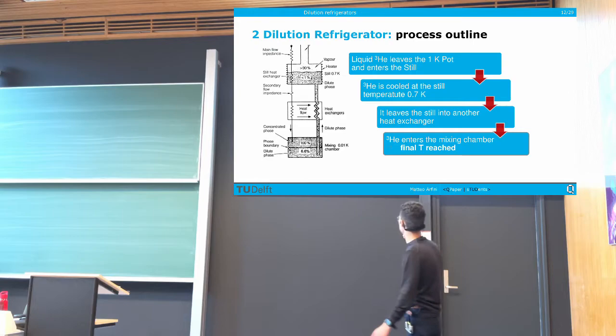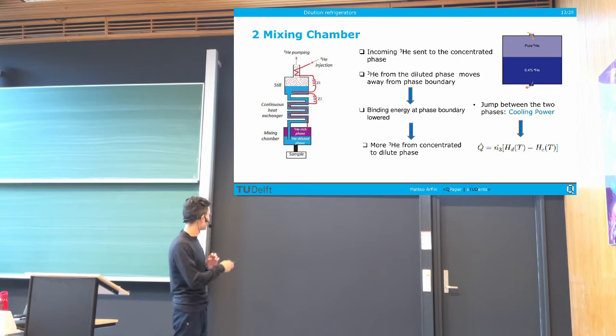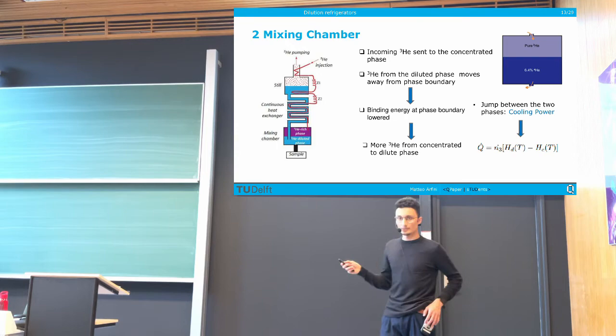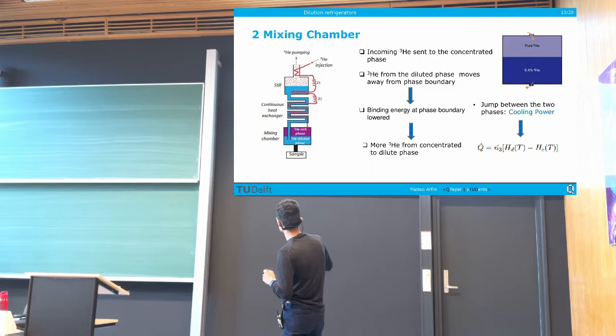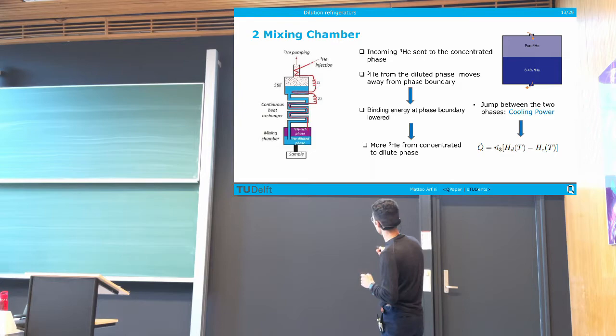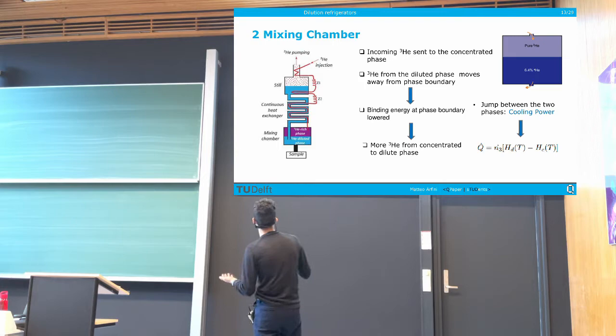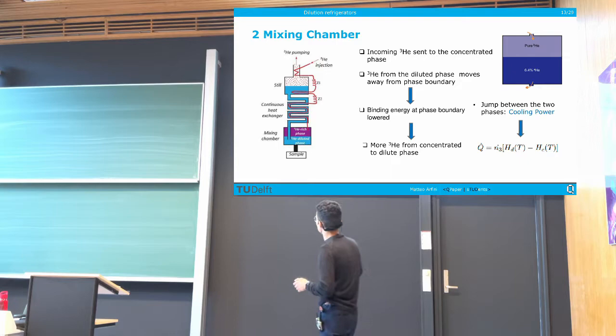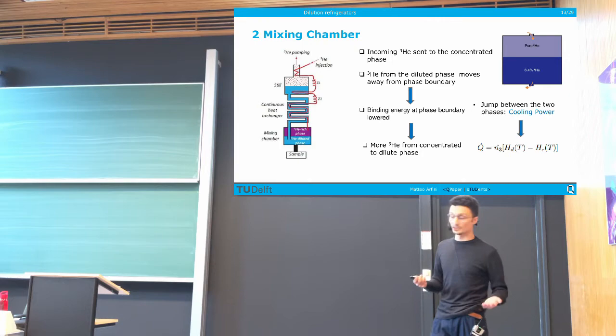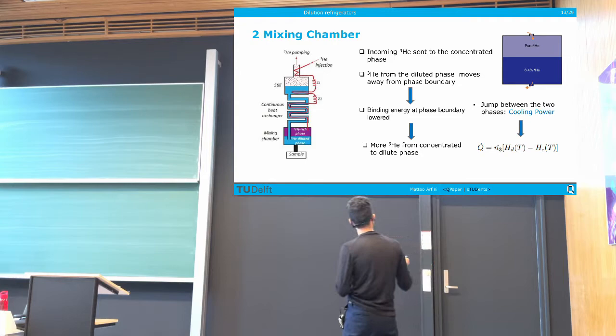So what is happening in the mixing chamber? Helium-3 enters the mixing chamber from the concentrated phase. If we are able to extract atoms of helium-3 from the dilute phase at the bottom of the mixing chamber, then helium-3 atoms move away from the phase boundary. This lowers the binding energy at the boundary, taking the system out of equilibrium, so helium-3 atoms jump from the concentrated phase to the dilute phase. This jump costs kinetic energy, so we are producing cooling — this is the cooling power of the system.